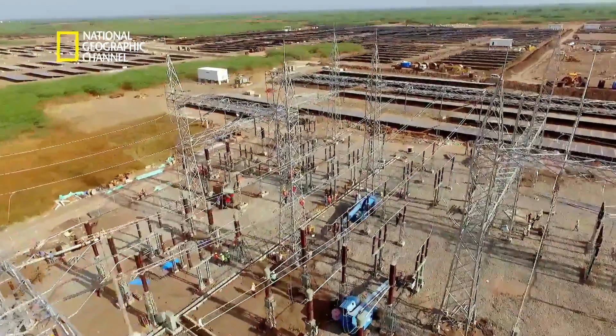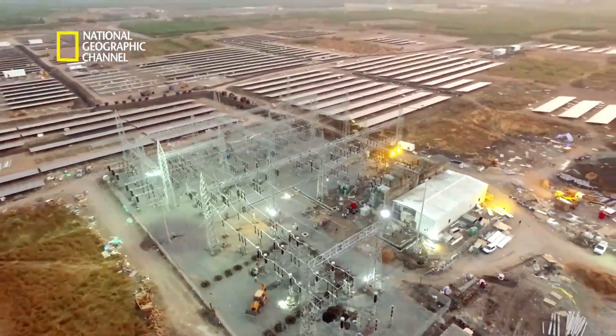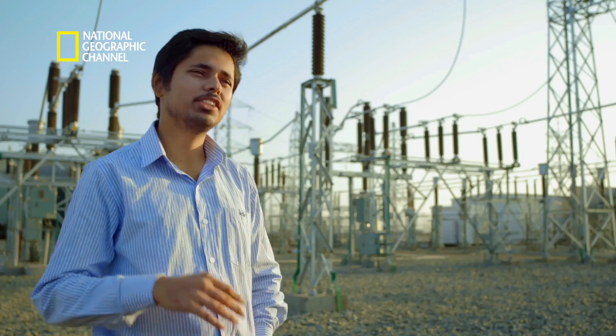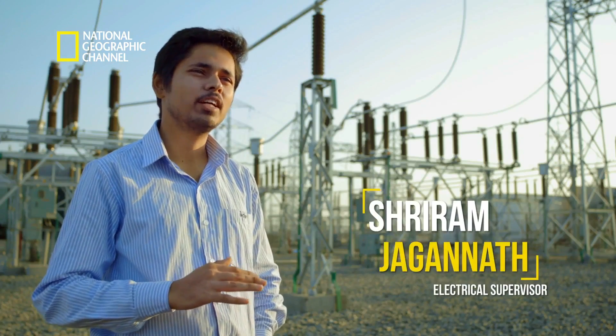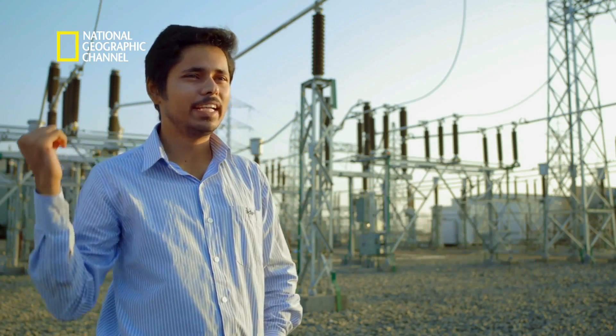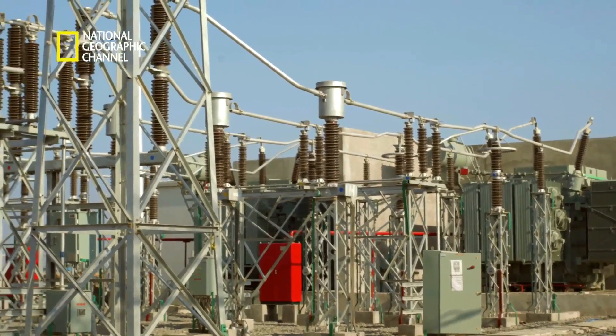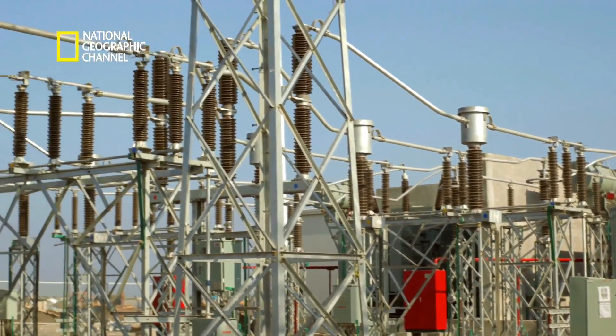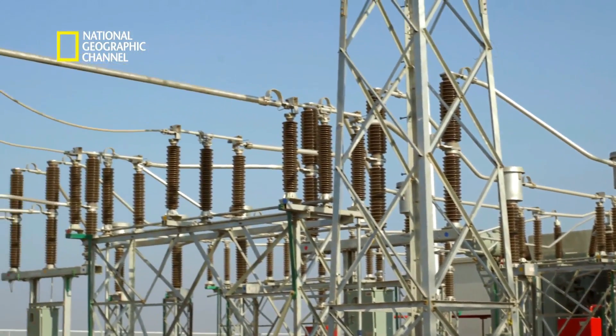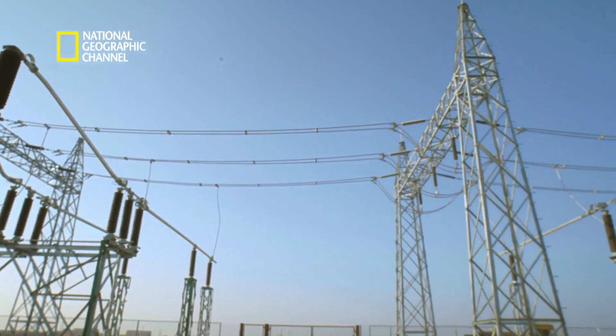At the end of the day, when it comes to electricity, a grid has to always remain stable. Typically in a solar power plant, generation stops around 6:30 in the evening, but we need power to run equipment like SCADA, lighting systems, and so on. So we take back power from the state electricity board — this is called a backflow. Essentially, backflow is us taking power from the grid to power our systems whenever we are not generating power.